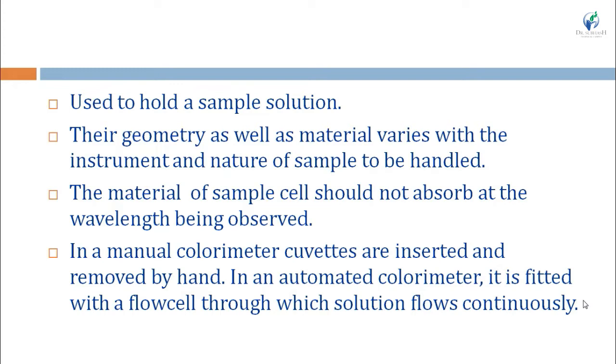The first condition of the sample holder is that the material of the sample cell should not absorb the wavelength which is to be determined.